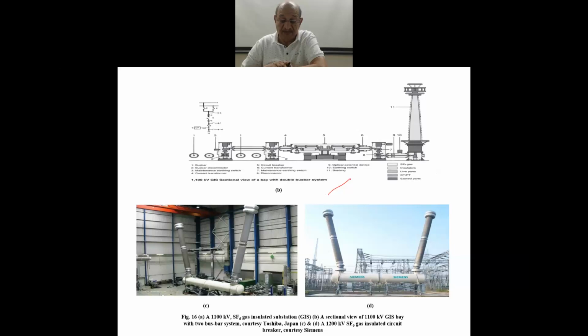And in picture C and D, you see a 1200 kV SF6 gas insulated circuit breaker. In C, this is the circuit breaker, SF6 gas at 1200 kV rated voltage, by Siemens. Imagine, of course, the bushings have to be very big. As you can see, the bushings for 1200 kV have to be very big. But the circuit breaker chamber comparatively is very small. So this is how the SF6 gas has found its application in power apparatus.